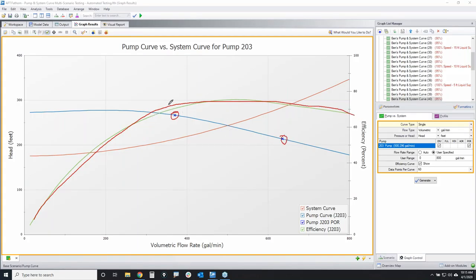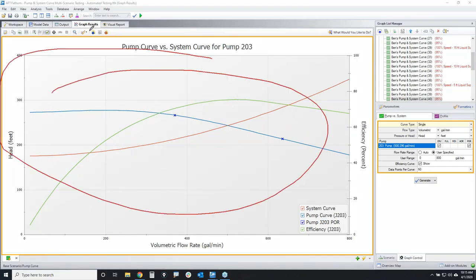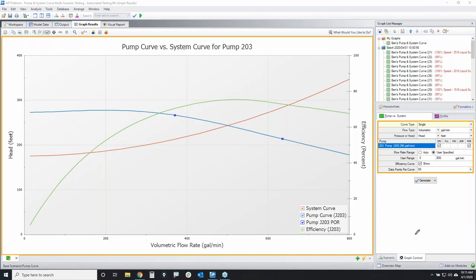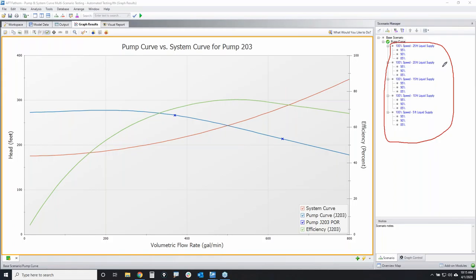There's the pumping system curve with the efficiency curve overlaid on top, and these little X's mark off the low and high levels of the preferred operating range in relation to the best efficiency point. Then you click on the folder icon with the blue plus sign — what I did was file this graph away in my Graph List Manager as a graph list item. This is a template that I prepared because I want to plot a pumping system curve for all of my different scenarios.